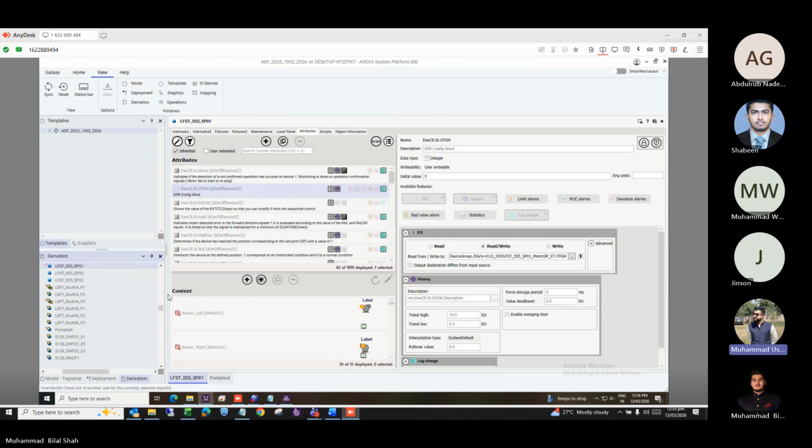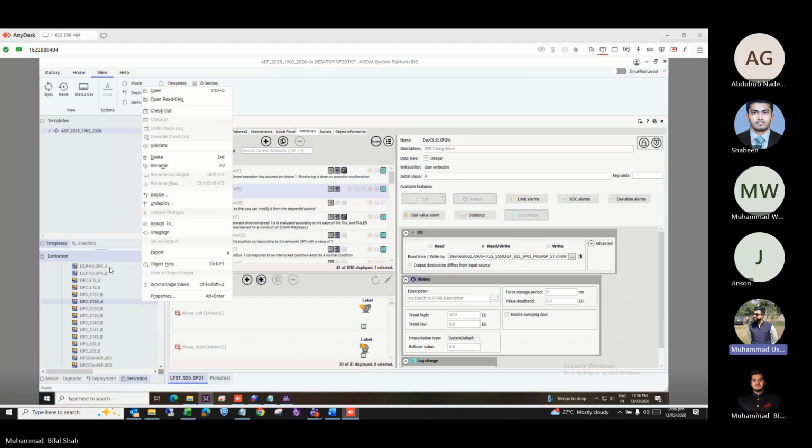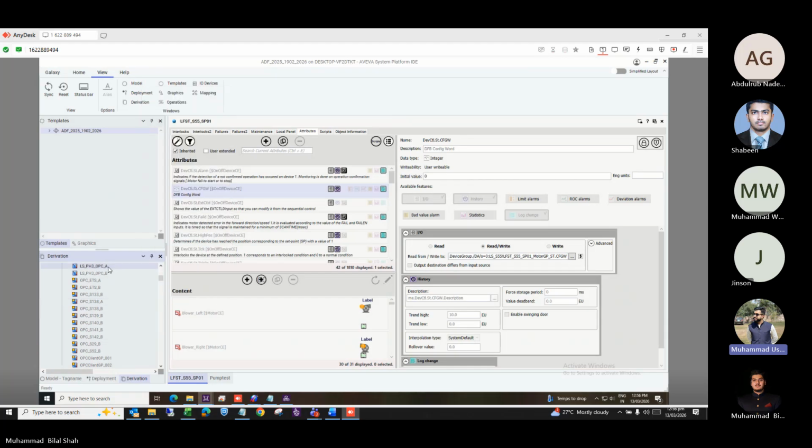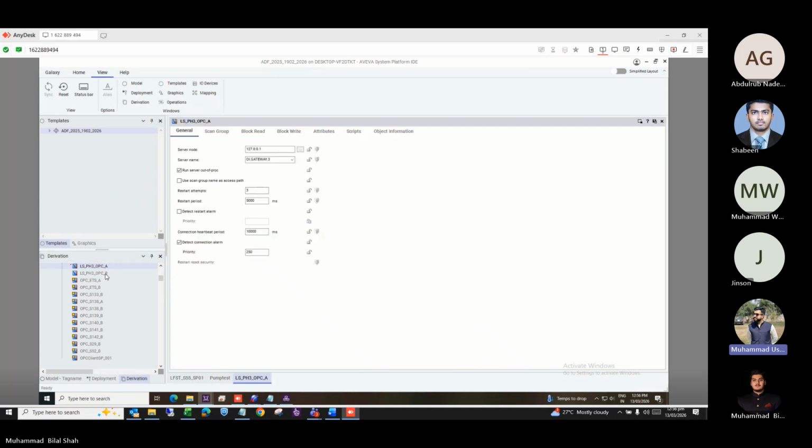The main source object which is actually connecting with the driver is the DI object, device integration object. But usually for high availability, as I explained earlier in the presentation, we do the redundancy on the device integration object level as well. For example, if we have two separate IO servers and we want to get the data from two separate sources, from our development perspective, to communicate the same object with two different IO servers, it is always advisable to use RDI.